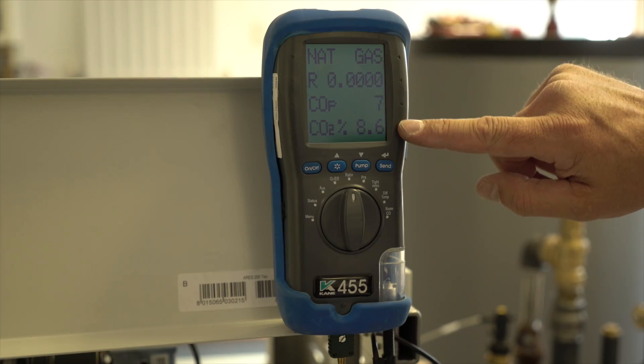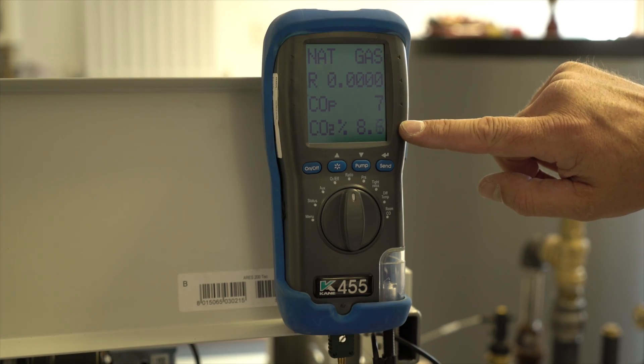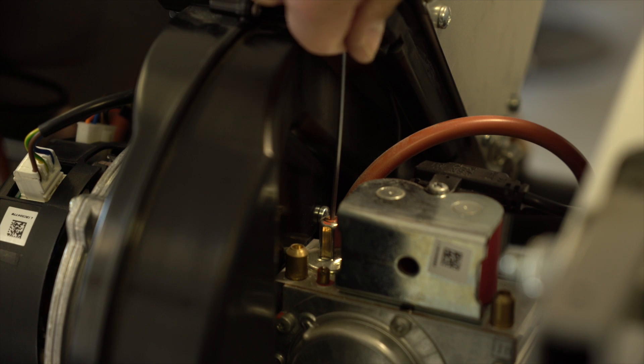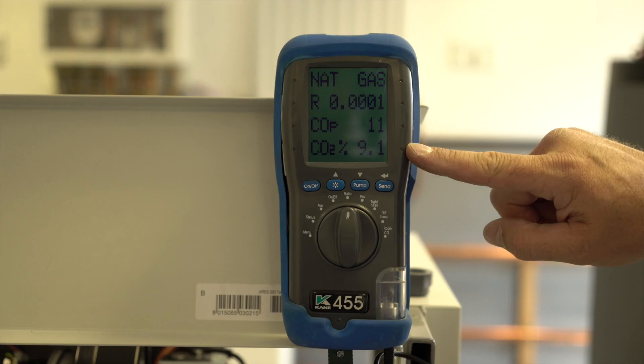Ensure CO2 values are correct. Adjust minimum screw on gas valve if necessary.